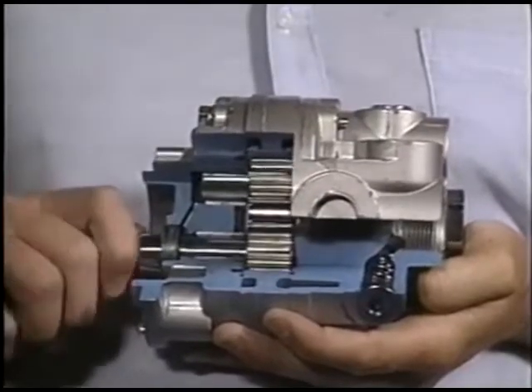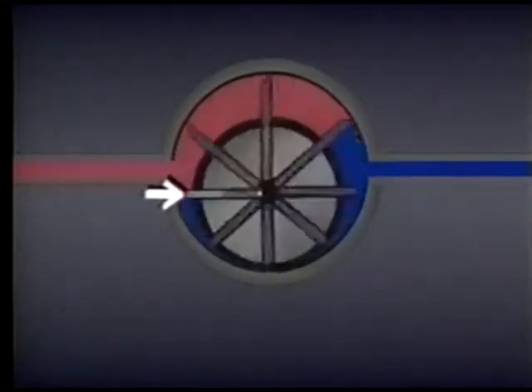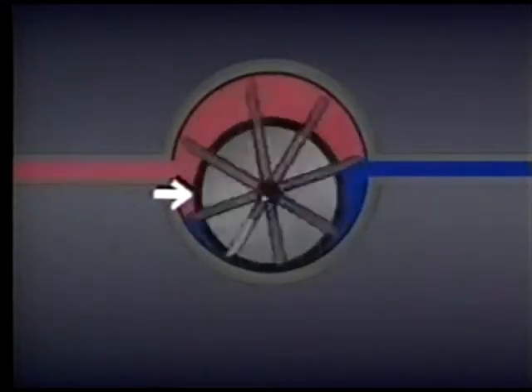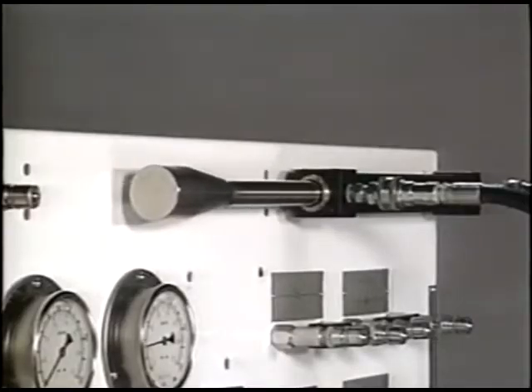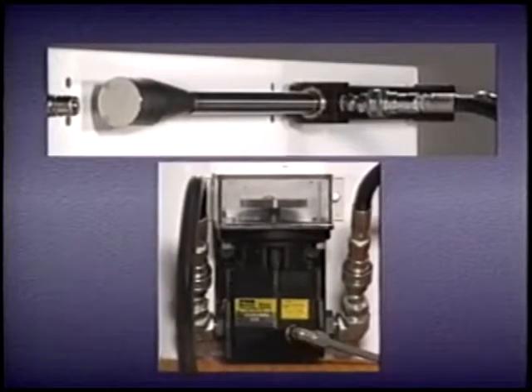The motion can also be circular or rotary, like a motor. In a motor, the shaft is attached to a rotating group, which turns as pressurized fluid enters one side of the motor housing and exits the other side. The rotating group is positioned off-center in the motor housing. This offset exposes more area of the top vane to system pressure than the lower vane. As a result, the force on the vanes is unbalanced and the shaft turns. The basic operating principles of all actuators are the same, whether they operate with linear or rotary motion.